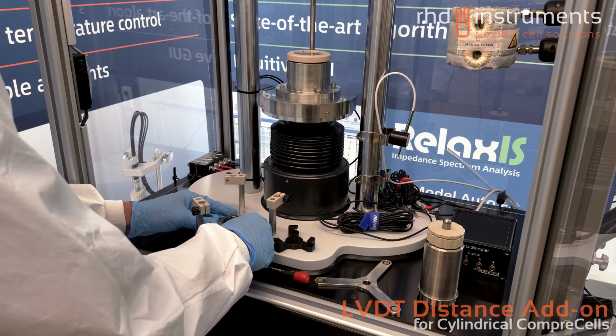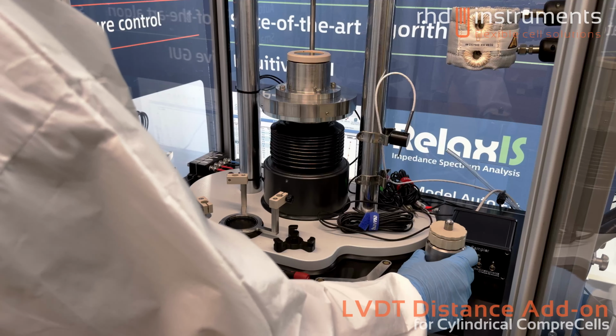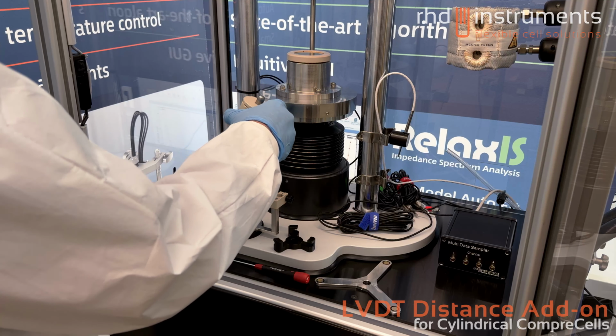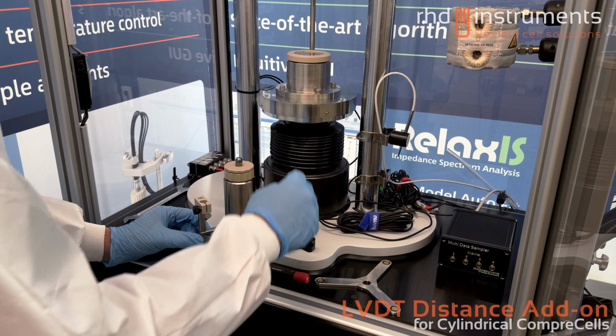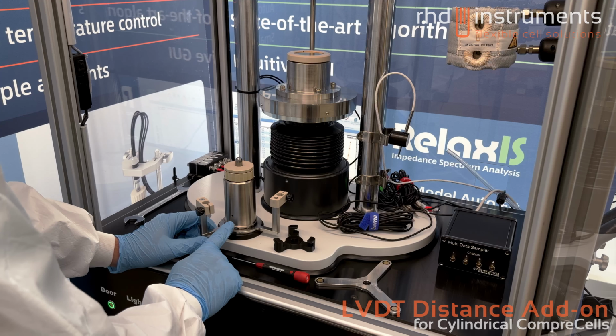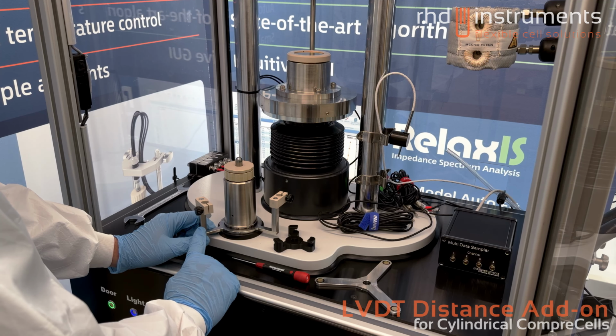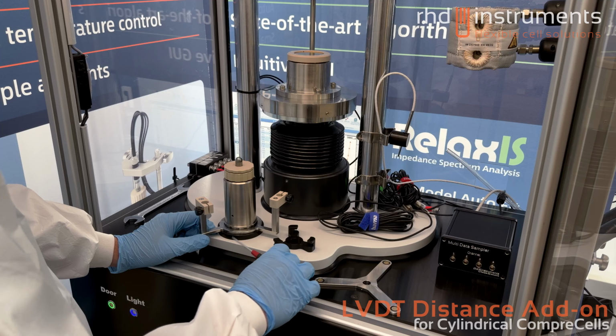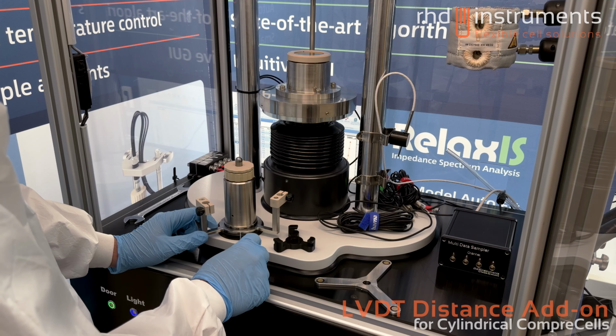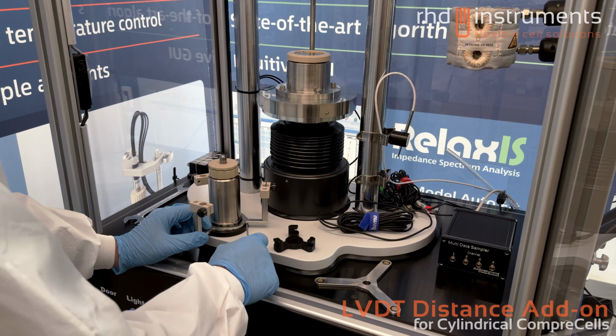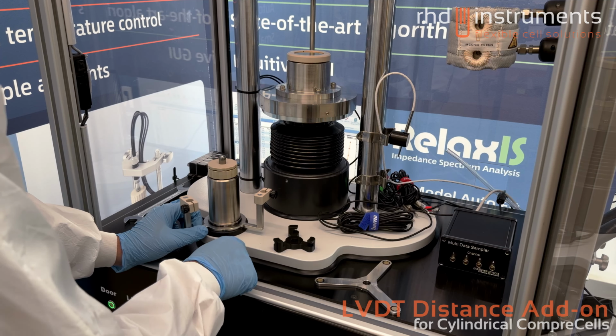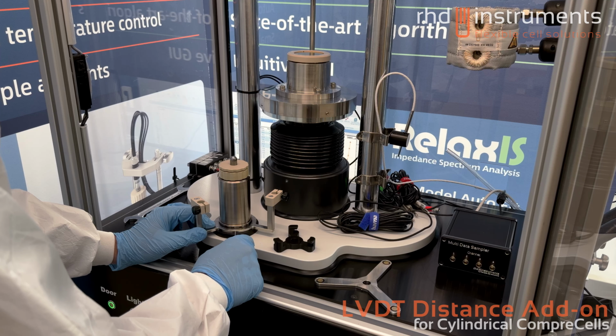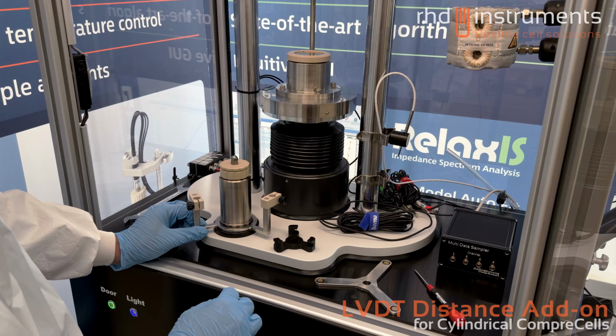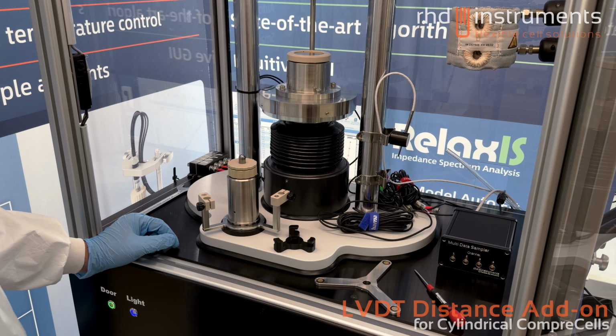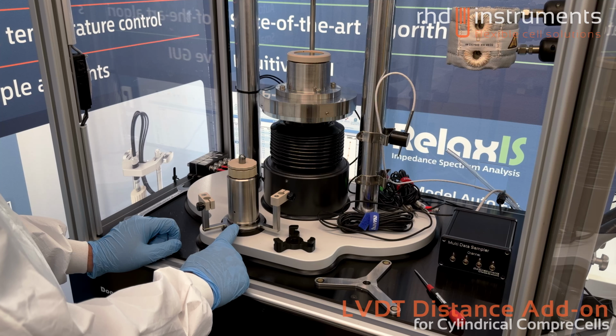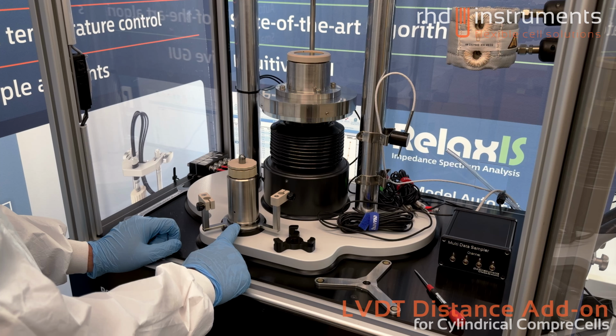First we want to mount the bottom sensor holder on the cell. We will place the sensor holder on the mounting aid and insert the cell into the mold. Make sure that there is an angle of 20 to 30 degrees between the sensor holder on the left and the temperature probe insert. Now I can tighten the grub screws and fix the bottom sensor holder on the cell. It is important to align the cell in a way that the grub screws do not touch the grooves in the base plate, but the protrusions.